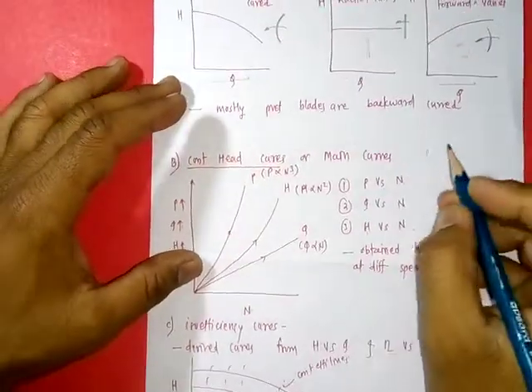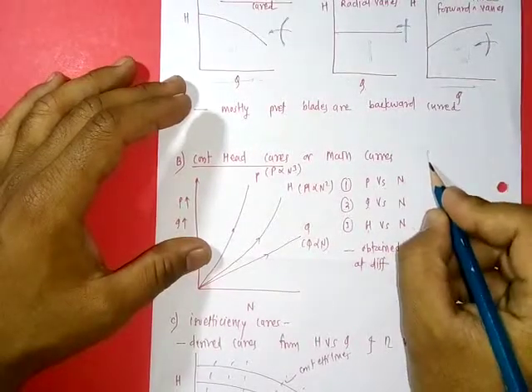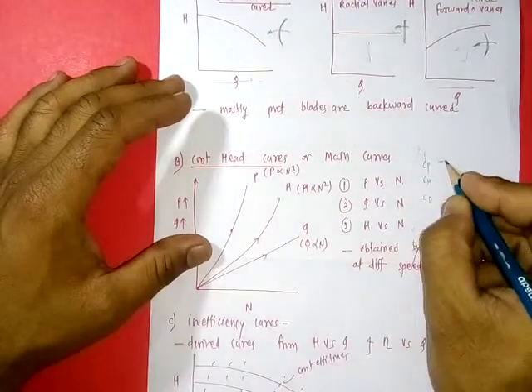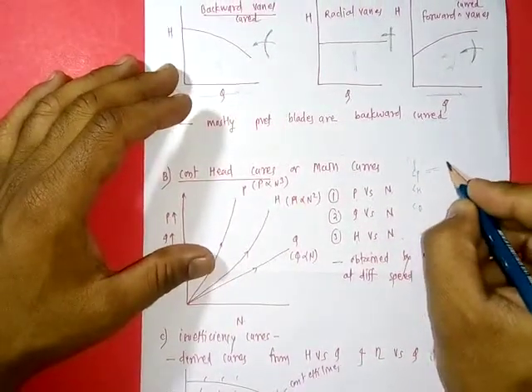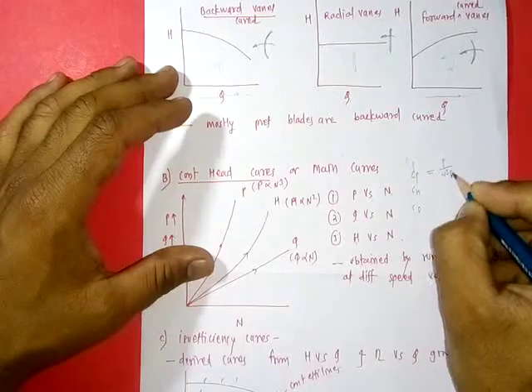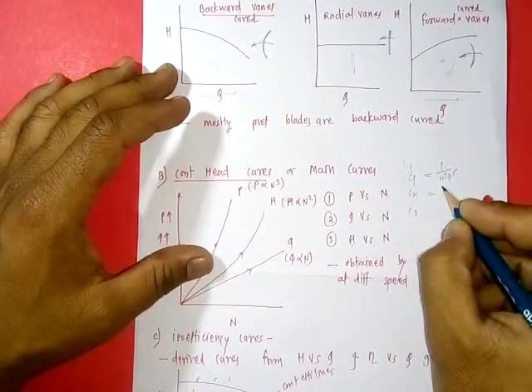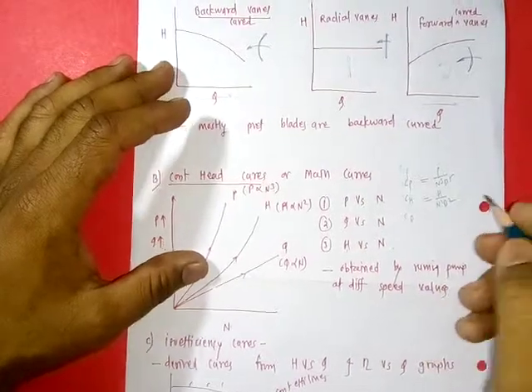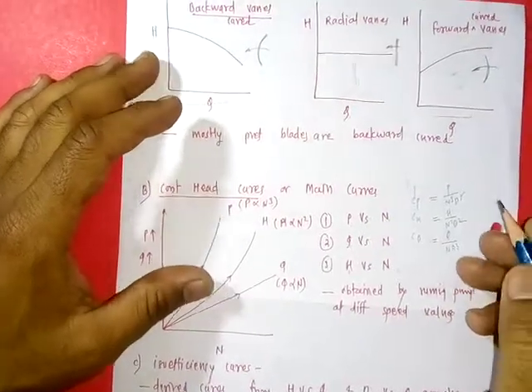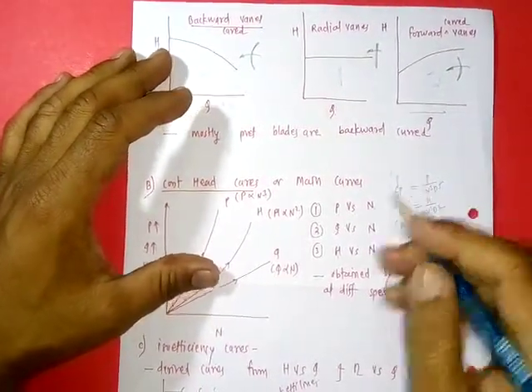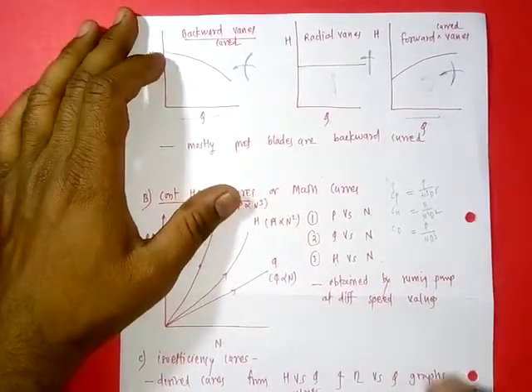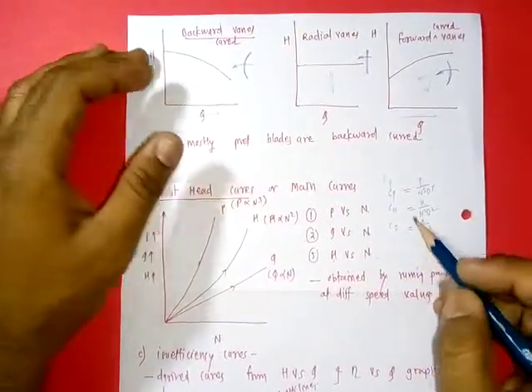For model testing we have the power coefficient, head coefficient, and discharge coefficient. Power coefficient is P/(N³·D⁵) = constant, head coefficient is H/(N²·D²) = constant, and discharge coefficient is Q/(N·D³) = constant. These were seen in the video on model testing of turbines — please refer to that for more details.